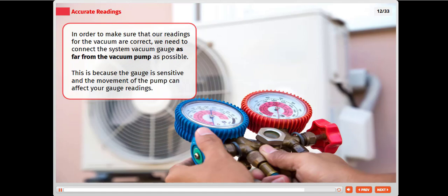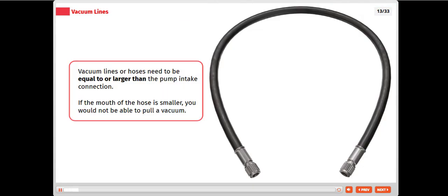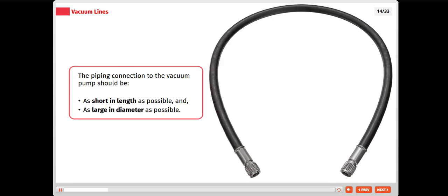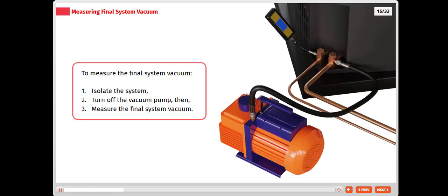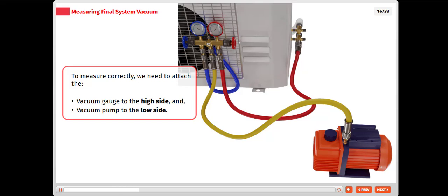Vacuum lines or hoses need to be equal to or larger than the pump intake connection. If the mouth of the hose is smaller, you would not be able to pull a vacuum. The piping connection to the vacuum pump should be as short in length as possible and as large in diameter as possible. To measure the final system vacuum, isolate the system, turn off the vacuum pump, then measure the final system vacuum. To measure correctly, we need to attach the vacuum gauge to the high side and vacuum pump to the low side.